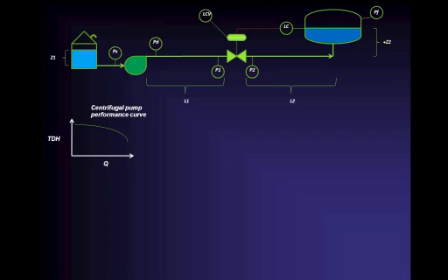And he says, "Well, Mike, that's your valve. You should know the differential pressure across the valve." And what we have here is a failure to communicate. We have a failure to recognize that we have too many unknowns and not enough equations to solve them. And actually, you are responsible for knowing the P1 and the P2, the valve inlet pressure and the valve outlet pressure, and you have to tell your valve manufacturer what that is as a function of flow if you want to end up with the best, most perfect control valve. So let me explain how this works.